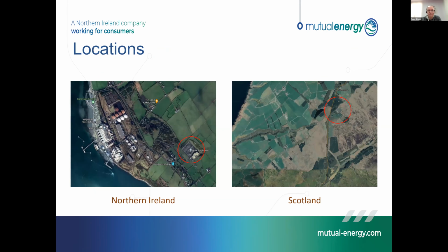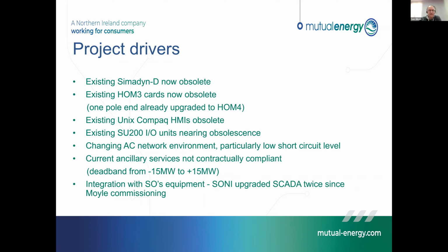In terms of the drivers for our project, obsolescence was the main thing. We were starting to see obsolescence on the key Siemens PLCs, on the optical measurement systems, one of which was upgraded some years ago, but even that HOM4 upgrade is now obsolete. We're still using Unix Compaq HMIs from the late 90s. Our input-output units are approaching obsolescence. I've mentioned the changing network conditions, and particularly the low short circuit levels. And then an issue that we were dealing with on our DS3 services to SONI and EirGrid: we do have a deadband. The LCC technology prevents us from operating between -15 and +15 megawatts, and for some of the fast frequency response services, that deadband was an issue. So we've come up with some novel approaches to deal with that in the upgrade.